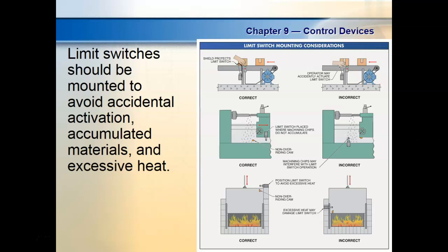Here they got it where it gets metal shavings in it. The top one, yeah, here they got a shield around it. I've seen that happen too, where people get in there trying to work on something and they actually accidentally activate the limit switch.